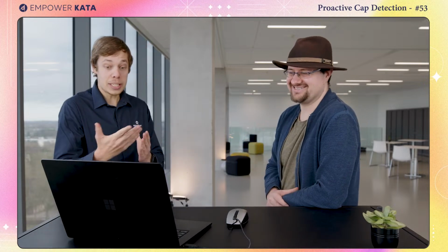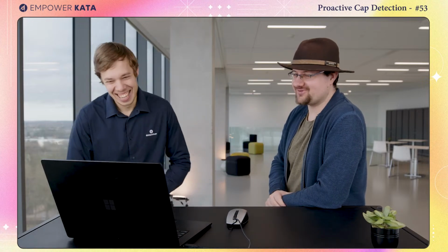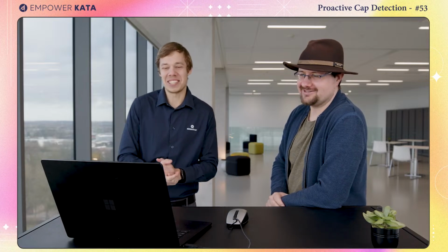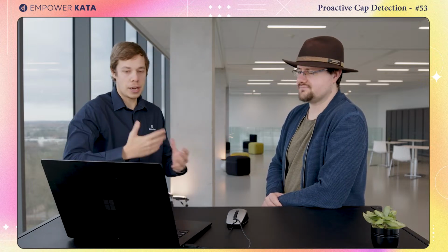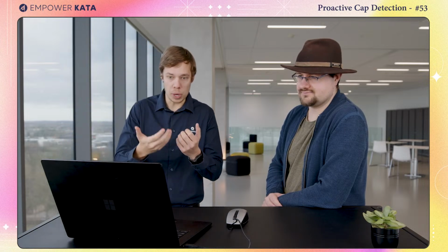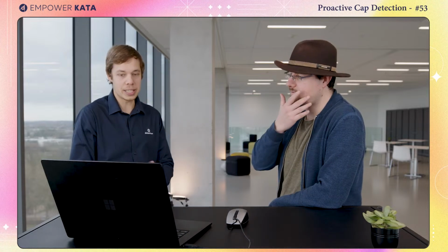This is created by a feature that we call proactive cap detection. It's a fancy name. We like fancy names. But it does describe what it does. In the background, it will go over all your parameters and make a prediction. When certain thresholds are reached, in this case the maximum value of the range, it can also be the lower value of the range, and there are some other thresholds that it takes into account, if a parameter will cross or hit one of these thresholds, it will make a predicted alarm.